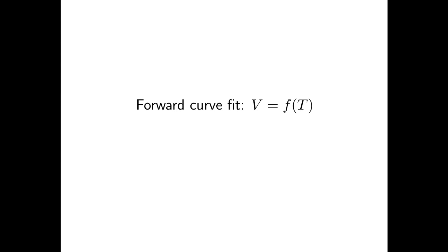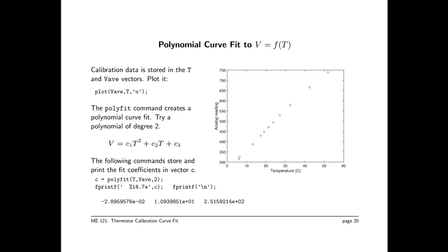First, we're going to do the forward curve fit, which is just fitting the data as if the purpose was to measure voltage as a function of temperature. Here's a plot on the right that was created with this command, plot Vav, T, circles. And we have already stored Vav, meaning that's the average reading at each of the temperatures. Using the polyfit command, we can create a polynomial curve fit. And for demonstration purposes, and in fact, for the actual calibration, a quadratic seems to work pretty well. The command C equal polyfit T Vav 2 executes the least squares curve fit and stores the results, the coefficients in a vector C.